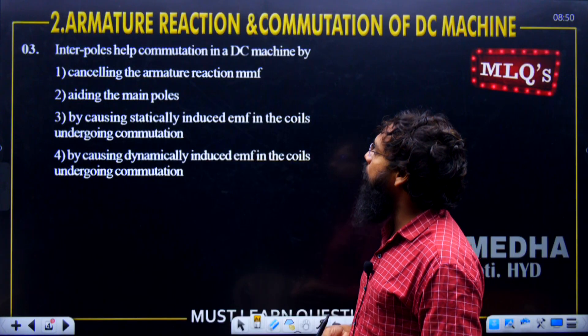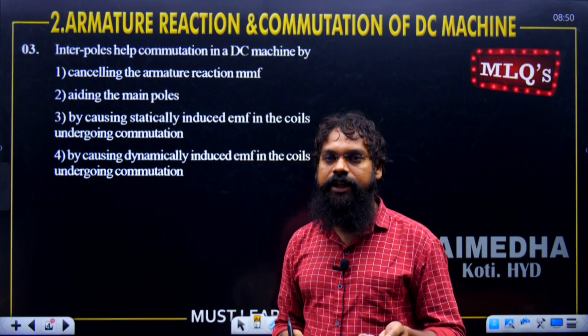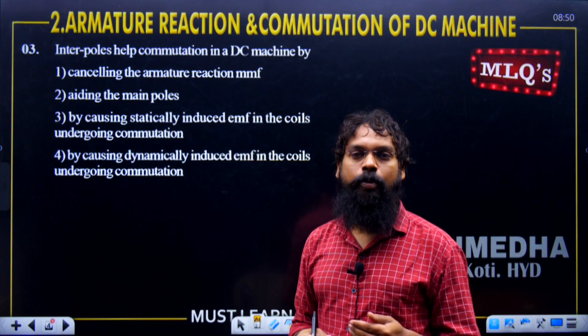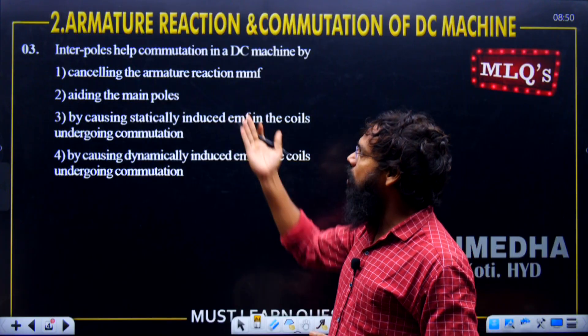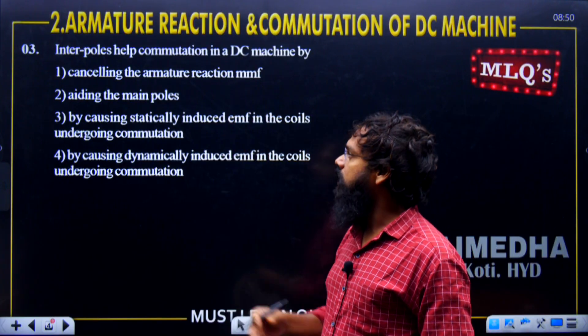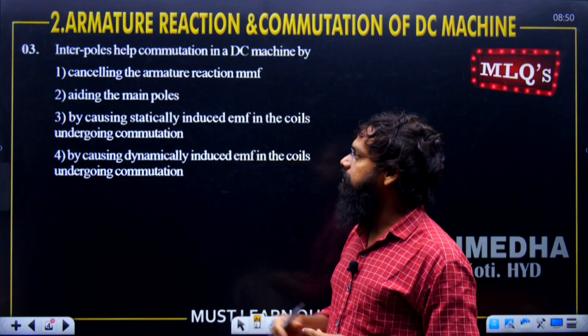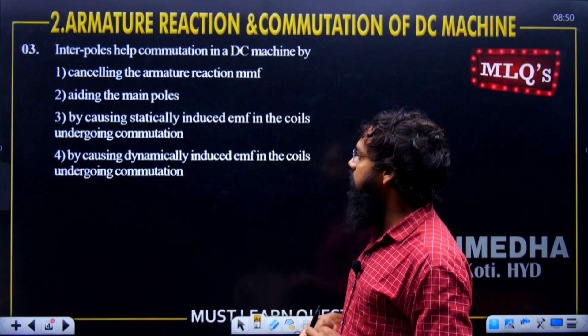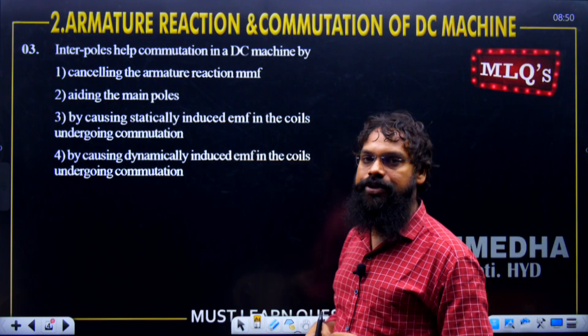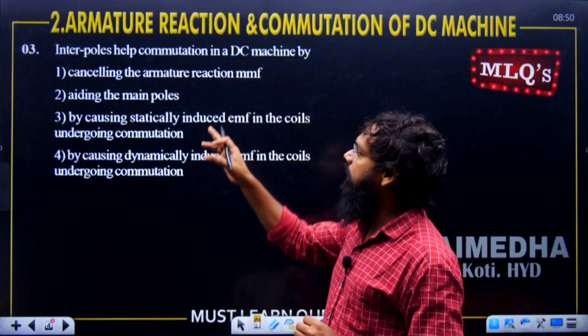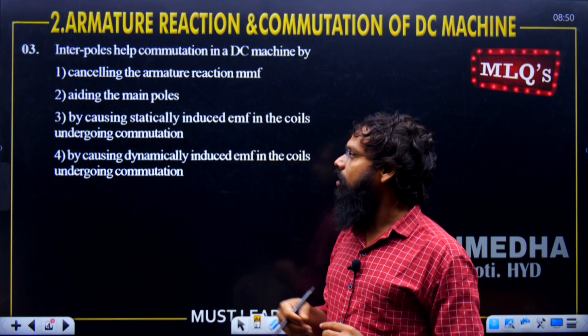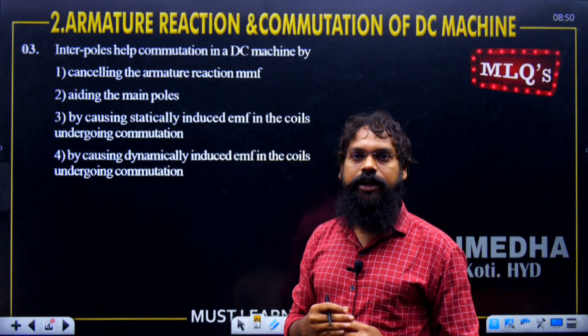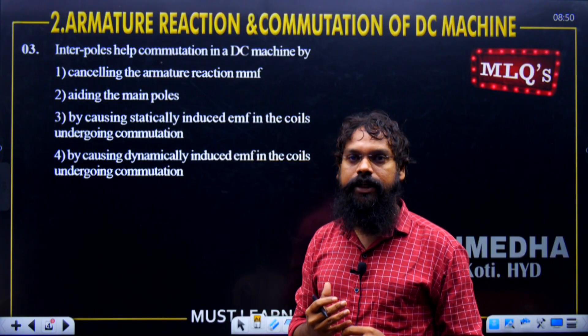Interpoles help commutation in DC machines. The function of interpoles is: to help and improve commutation; to cancel the armature reaction MMF; to aid the main poles; or to cause the statically or dynamically induced EMF in the coils undergoing commutation. What we do is neutralize the cross-magnetization effect.